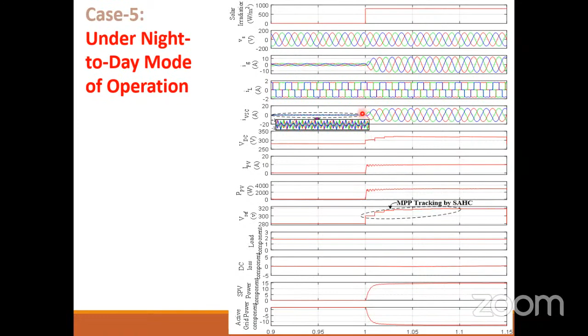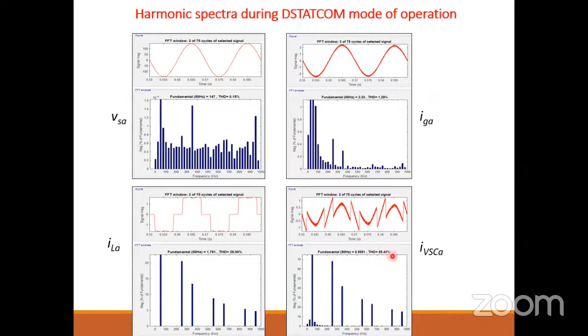Similarly, if you go for the harmonic analysis on the simulation side, in the night time mainly, you will see the grid voltage and the grid current. The grid current THD is, I think, 1.2%, but the load is 29%. On the inverter side, ideally the inverter is only generating the nonlinear current, so the THD should be what? Ideally, it should be 100%, because the inverter is only generating nonlinearity. Here the THD is 95.42%, right?